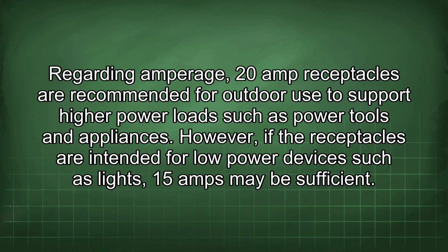Regarding amperage, 20-amp receptacles are recommended for outdoor use to support higher power loads such as power tools and appliances. However, if the receptacles are intended for low power devices such as lights, 15 amps may be sufficient.